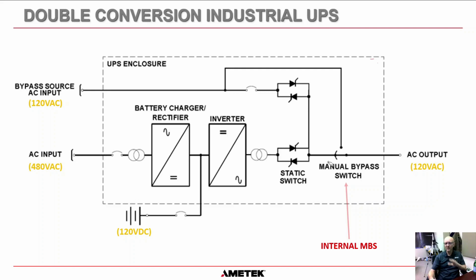And that becomes very important in just a moment. And also on this page, I'd like to refresh everybody on the difference between a static switch and a manual or maintenance bypass switch. The easiest way to understand it is that a manual bypass switch is usually a mechanical switch. In fact, it near enough always is a mechanical switch. It can either be an arrangement of switches, or for AMETEK Solidstate Controls, it is a rotary switch that has make before break contacts in it. So it's an actual switch that mechanically makes and breaks the circuits.